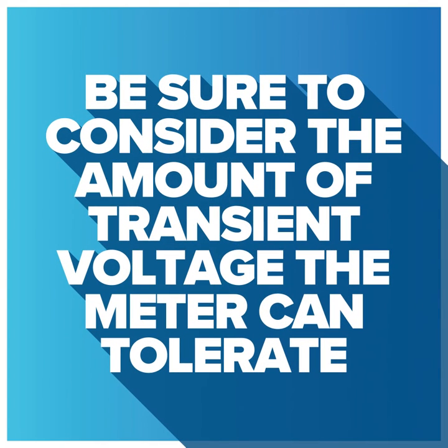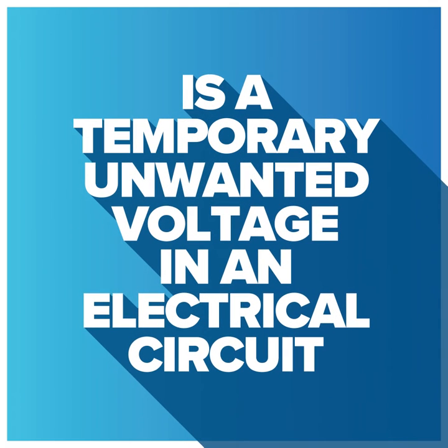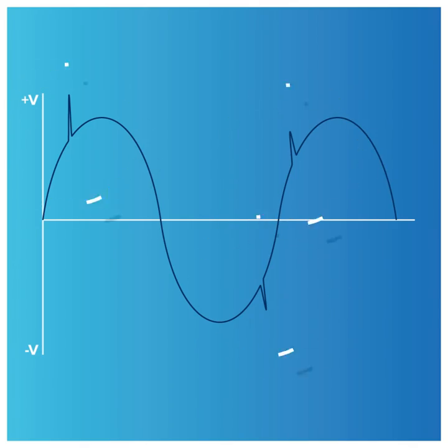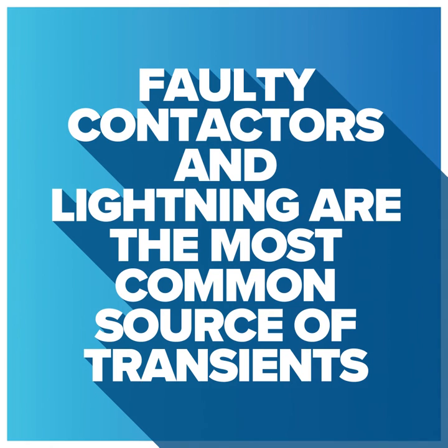Be sure to consider the amount of transient voltage the meter and meter leads can tolerate. A transient voltage is a temporary, unwanted voltage in the electrical circuit that ranges from a few volts to several thousand volts, lasting at least microseconds or sometimes milliseconds. Faulty contactors and lightning are the most common sources of transient voltage.